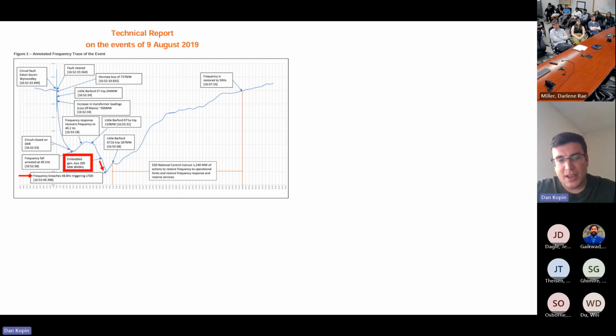You can see with that red box and that arrow going down that initiated under-frequency load shed protection. And when under-frequency load shed protection initiated, London lost power for 4 hours. So we are talking about the difference between a bad day and a really significant risk to public health and safety.